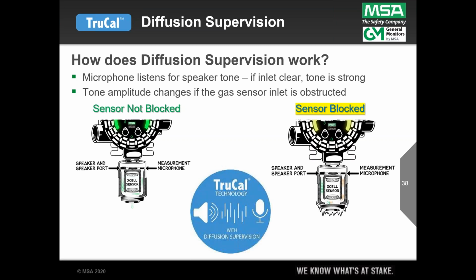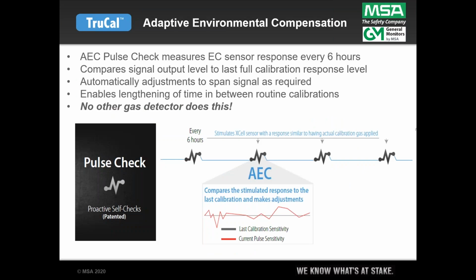But should there be some frozen ice or mud daub or something put some junk up in that opening of that sensor, which, normally you'd hope your technicians doing their visual walkthrough will catch, but we know from experience they don't always catch everything. So this is a built-in diagnostic. If the sensor opening is blocked and this detector can't do its job, not because it's failed internally but because something external is blocking it, this diffusion supervision will create a fault and let the technicians know on site we've got a problem with that instrument's capability to sense that gas. No one else has got this. It's a very cool thing, and it does it all the time, so you can count on this device to always monitor itself.